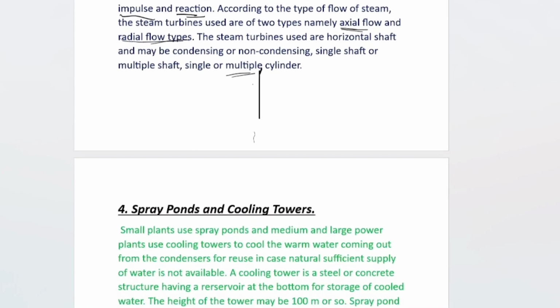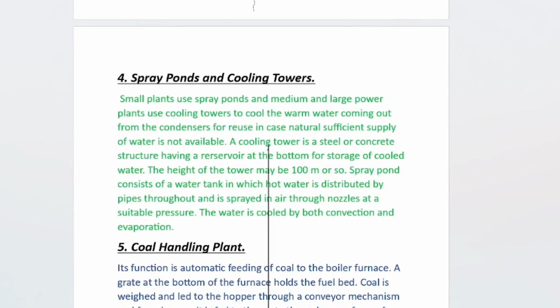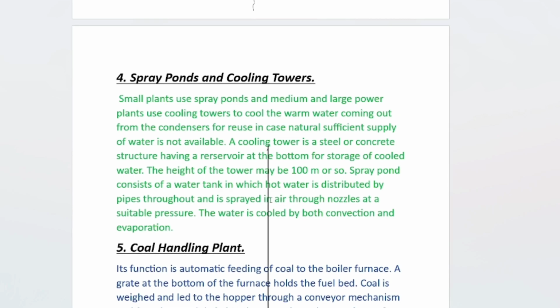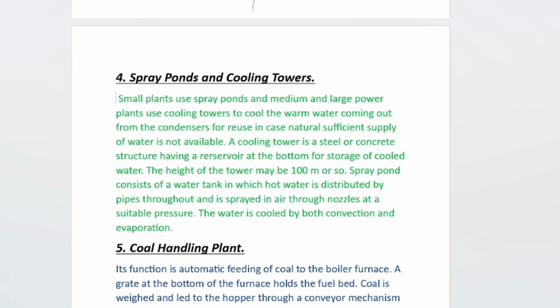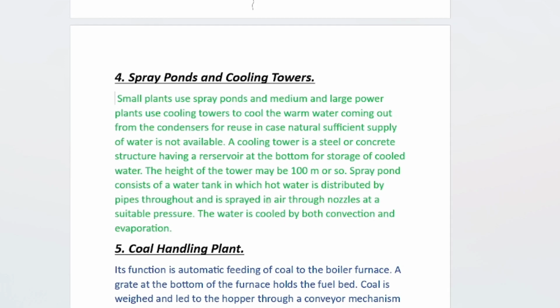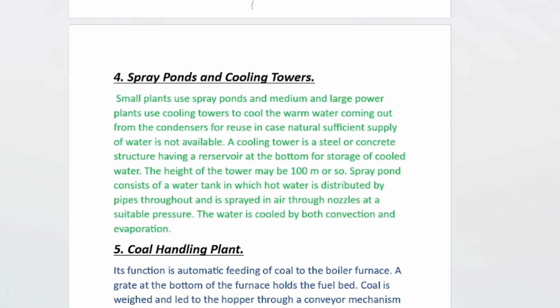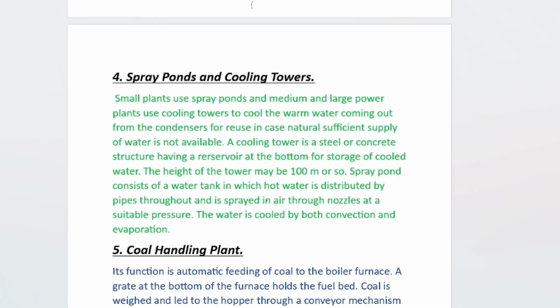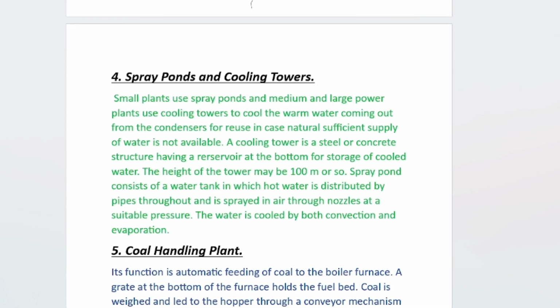Fourth part is spray ponds and cooling towers. Small plants use spray ponds and medium and large power plants use cooling towers to cool the warm water coming out from the condensers for reuse, in case a sufficient natural supply of water is not available.